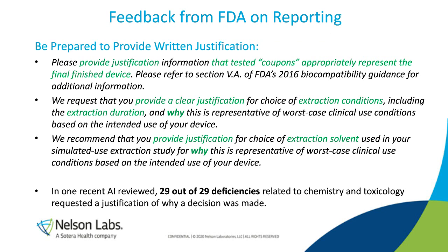Okay, so IDs and quantification, and then I wanted to touch a little on what they've been saying about reporting, especially when it comes to this idea in general of providing justifications. So just take a look at this series of FDA comments coming from a few different recent pieces of feedback. They said, please provide justification information that the tested coupons appropriately represent the final finished device. So it's not enough to just say, okay, we used coupons to represent the device. They want further explanation on why that's the case. Next bullet: please provide a clear justification for choice of extraction conditions, including the extraction duration and why this is representative of worst case clinical use.